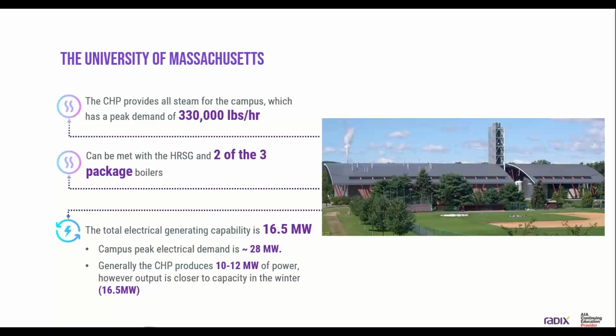So the campus peak steam load is about 333,000 pounds per hour. That happened to us in January, late January, early February. We can meet that campus demand with our HRSG heat recovery steam generation unit and 2 of our 3 package boilers. On the electrical side of the house, the central heating plant can generate 16.5 megawatts of power. Campus peak demand is 28 megawatts, which would typically happen in late August, early September as the students come back. Around that time, the CHP would be generating somewhere around 10 and 12 megawatts. But during heating season, we can generate 16.5 megawatts when we hit our peak steam loads.